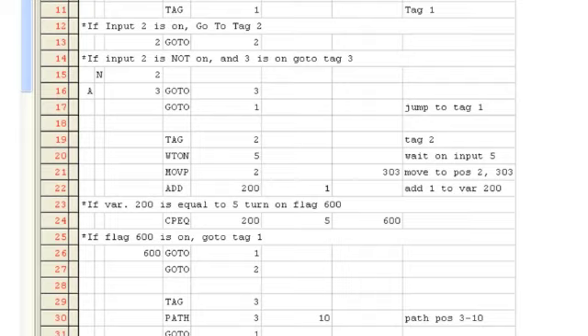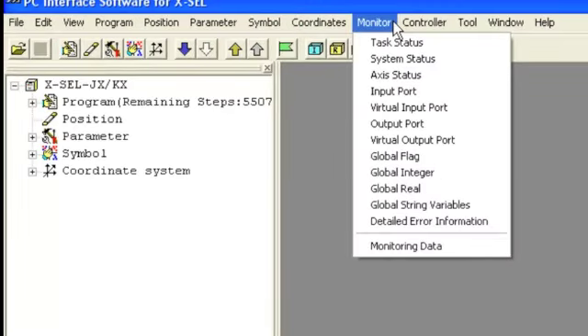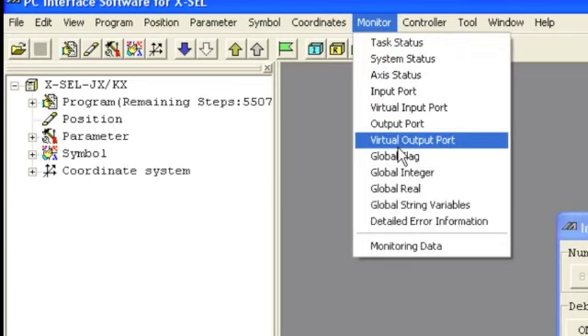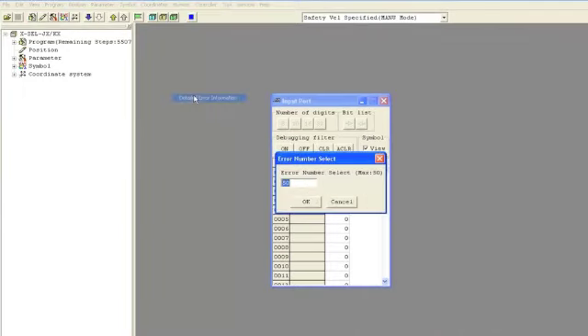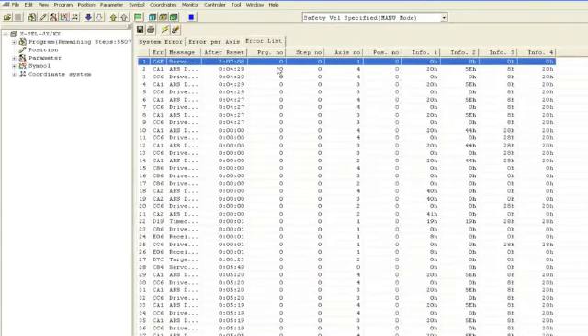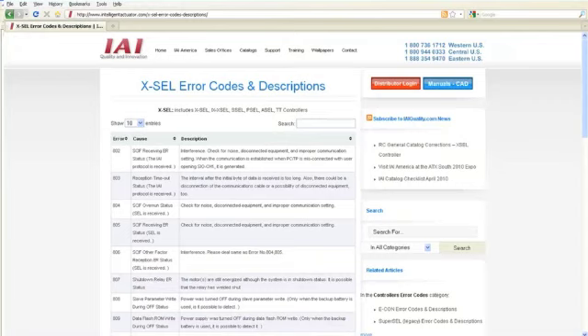This is a quick, simple program that shows you how to use each column in the position table. You can monitor the current state of inputs and outputs and see what values are stored in variables by using the Monitor menu. From the Monitor menu, you can monitor the task status, system status, axis status, input ports, output ports, as well as global integers, real numbers, and string variables. Also from the Monitor window, you can look at the Detailed Error Information, which stores all detailed errors with error codes, the program they occurred in, the step number, the axis, and the 3-digit error code. You can use this code to look up the error in the IAI programming manual or on the IAI website.